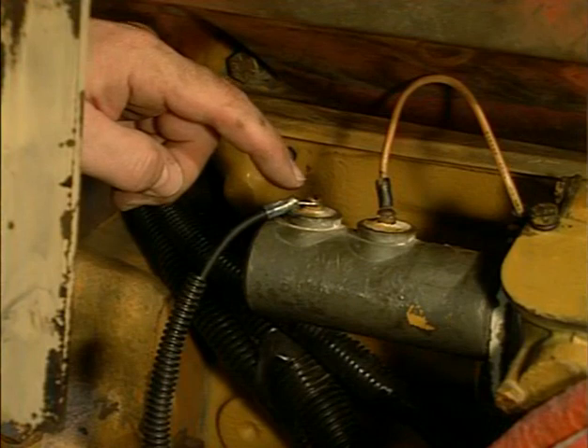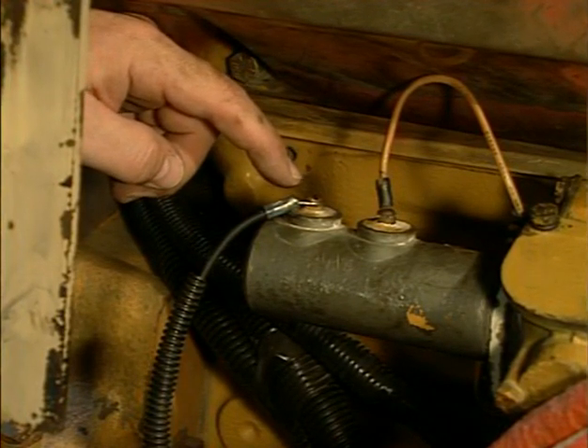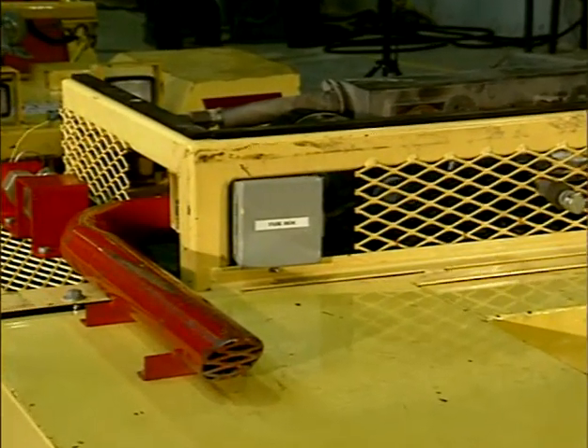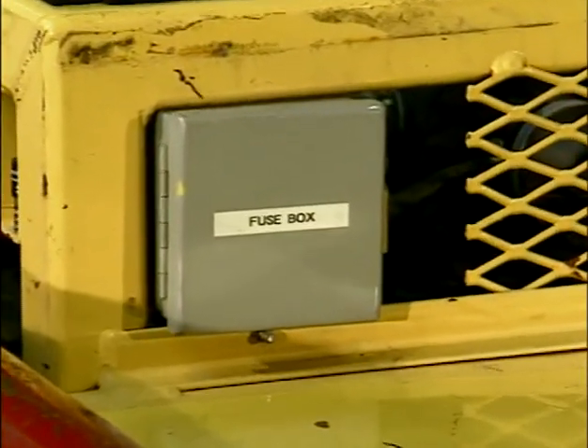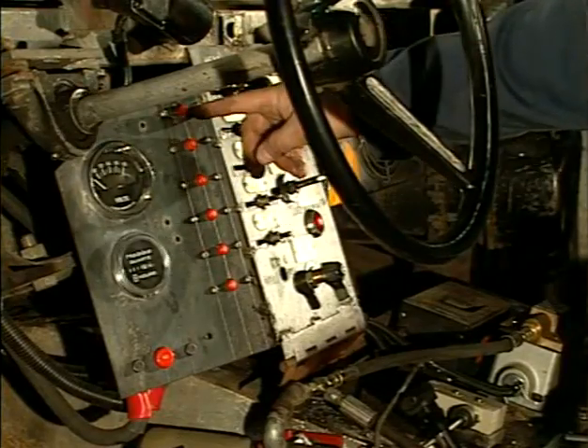The new regulation will require each ungrounded conductor to have insulation compatible with the impressed voltage. These connectors need to be insulated, and the insulation materials must be resistant to deterioration from engine heat and oil. Ungrounded connectors do not need to be insulated if they are enclosed in a box that contains only electrical components, such as this fuse box.